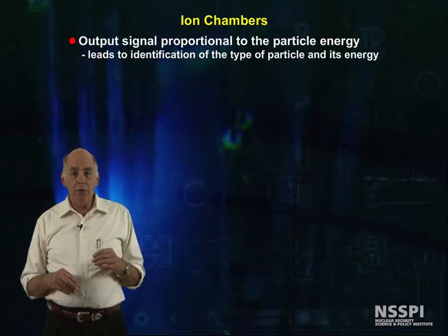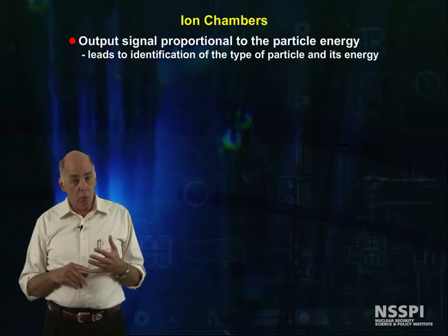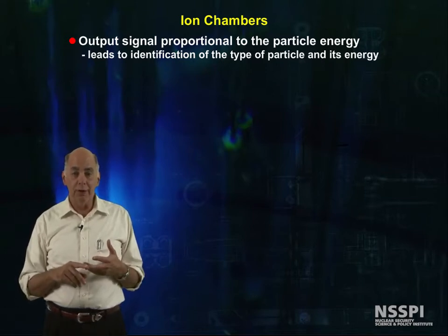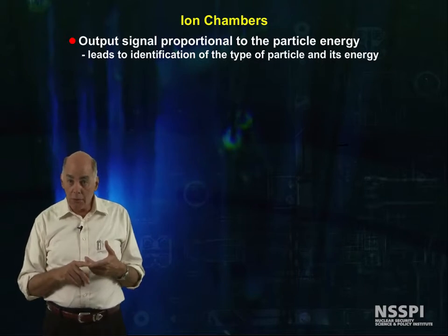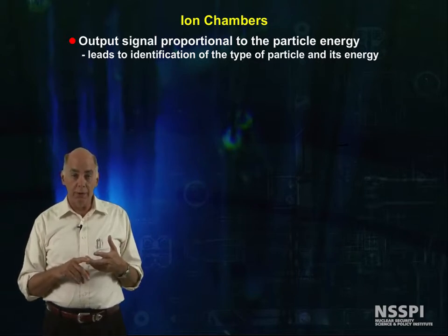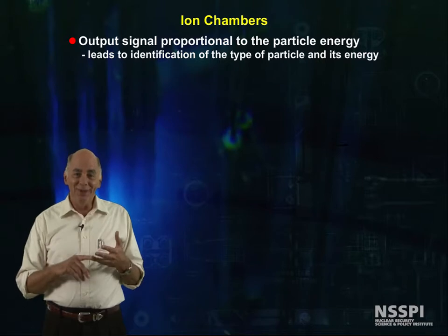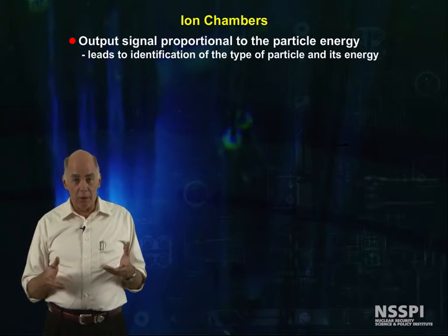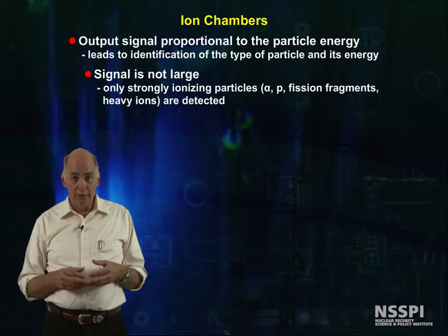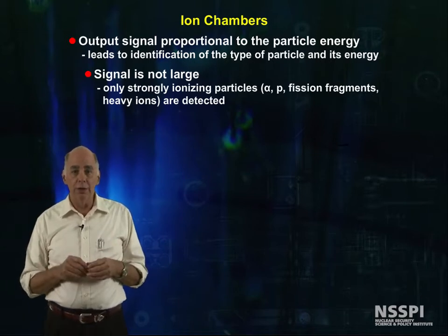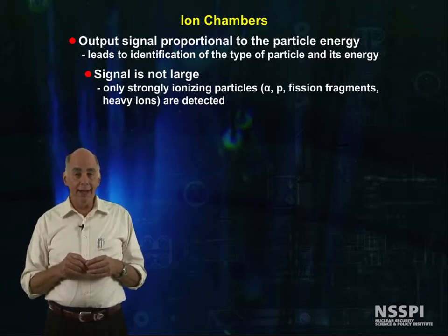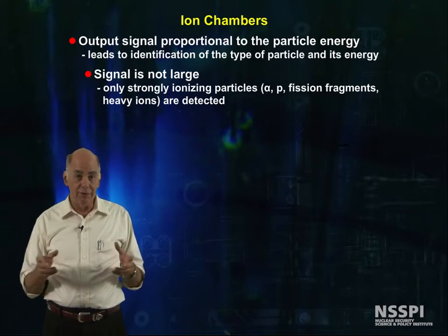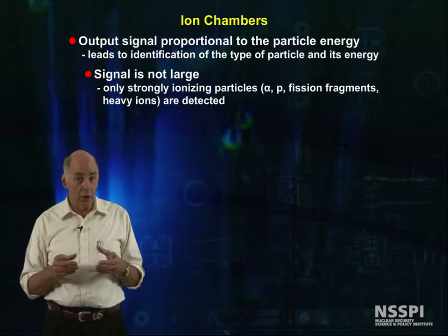In the ion chamber region, the output signal is proportional to the amount of charge deposited in the sensitive volume, which is in turn proportional to the incident particle energy. In principle, this could be used to identify the type of particle and its energy. But the signal is not large, and only strongly ionizing particles — for example, alpha, proton, fission fragments, or heavy ions — are detected.